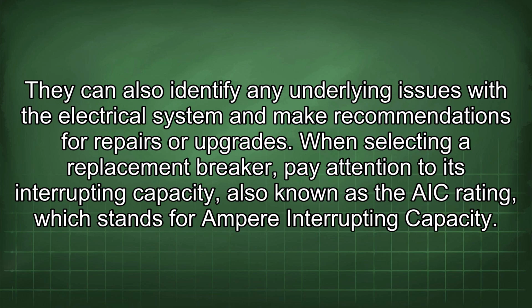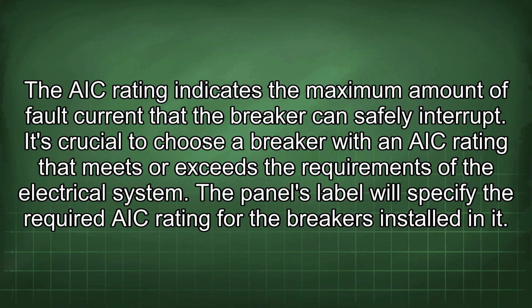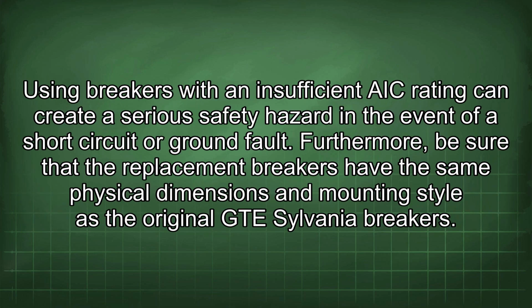When selecting a replacement breaker, pay attention to its interrupting capacity, also known as the AIC rating, which stands for Ampere Interrupting Capacity. The AIC rating indicates the maximum amount of fault current the breaker can safely interrupt. It's crucial to choose a breaker with an AIC rating that meets or exceeds the requirements of the electrical system. The panel's label will specify the required AIC rating for the breakers installed in it. Using breakers with an insufficient AIC rating can create a serious safety hazard in the event of a short circuit or ground fault.